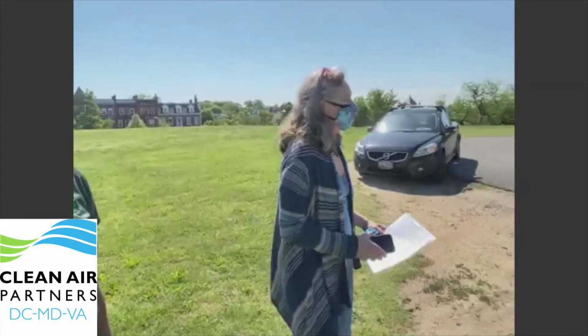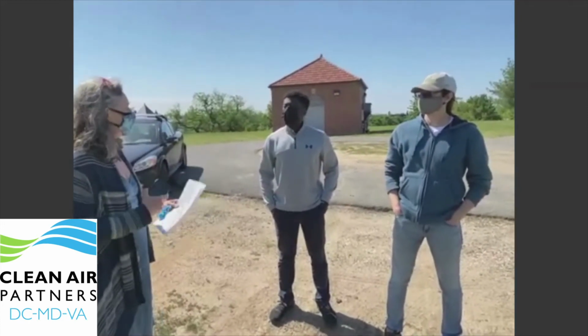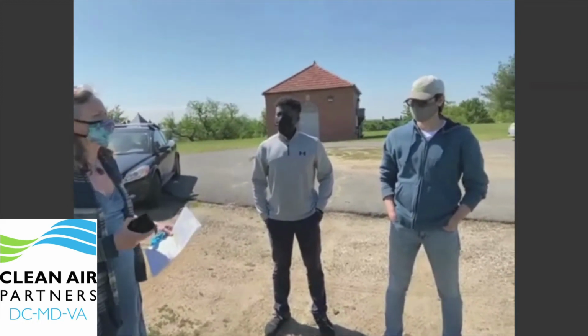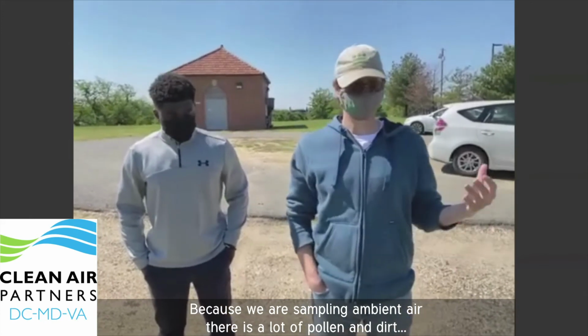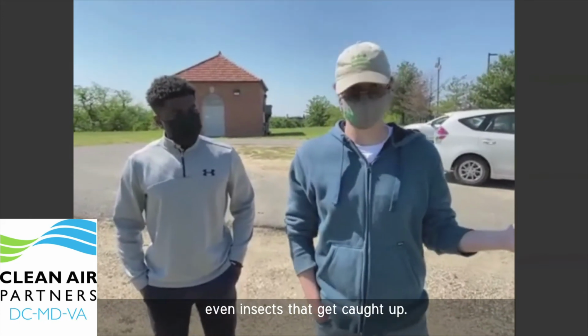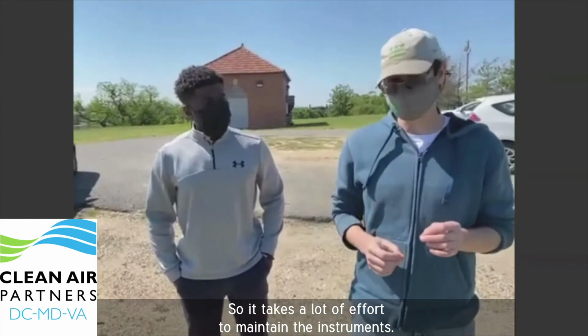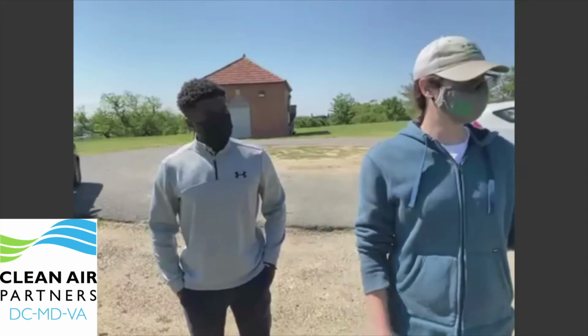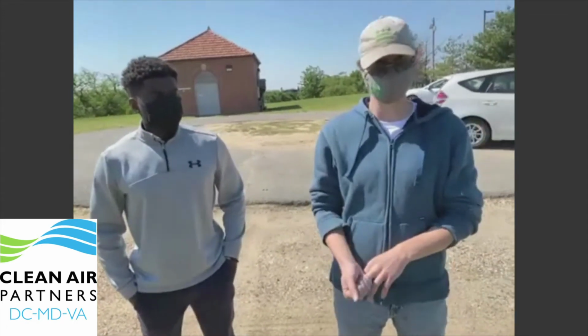All right, Cameron and Kane, can you guys talk about the day-to-day quality control and other tasks that you do here to keep the instruments going and for the data to be accurate? So because we have so many things and they're sampling ambient air, there's going to be a lot of pollen, a lot of dirt, a lot of biological matter and insects that get caught up, which is unfortunate. It takes a lot of effort to maintain these devices to keep them reading accurately. So probably once a month for me, every single thing you saw up there, I have to clean it. I have to clean the down tube. I have to change the filters. I have to do all that stuff.